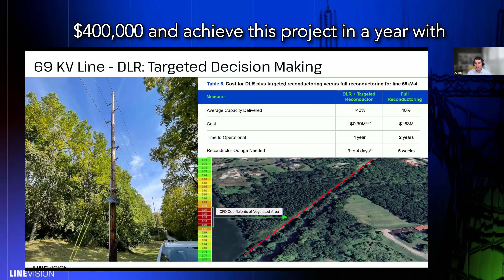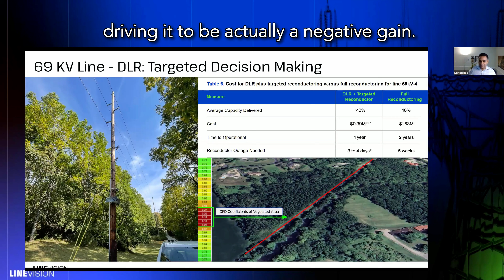This insight wouldn't have been available without DLR, and it allows us to target our capital and deploy it efficiently to serve our customers. Once you've addressed that one limiting section, you unlock the benefit of DLR across the entire line. We saw something like a 10% gain in capacity overall, except for this section, which was driving it to actually be a negative gain. So you have a win-win of getting the proper capacity even with your existing rating, but then going even higher by unlocking the DLR capacity on the rest of the line.